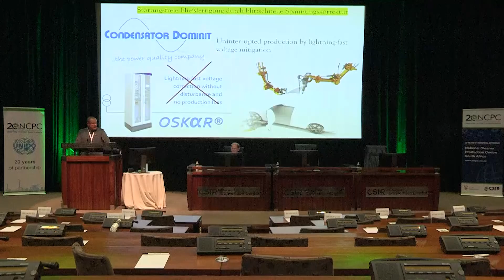So what is done? Let's look at a typical example of a voltage dip. Voltage in this case sits at any value. Let's make it 10.5 kilovolt. And somewhere in the network is a short circuit, so the voltage just drops off. Normally this is how it happens, very fast, and it will recover a bit slower. But there's a period of time where, per definition, when it goes below a certain threshold, it will be defined 10% below the nominal. If that is 11 and that is 10.5, so that will be at 9.9 kV.